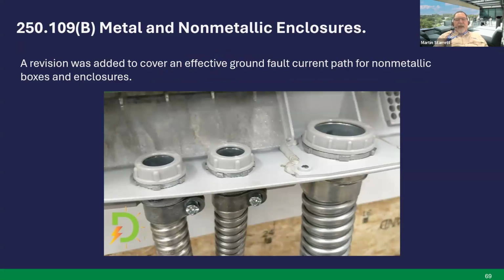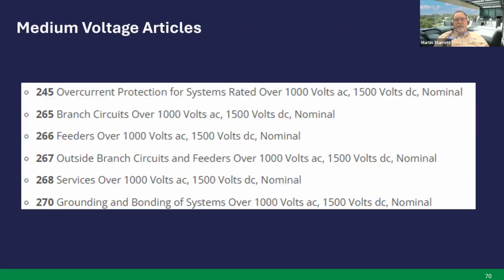250.109(B), metal and non-metallic enclosures. A revision was added to cover an effective ground fault current path for non-metallic boxes and enclosures where metal pipe and raceways come into these non-metallic boxes. It tells you how to do your effective ground fault current path for these whenever you do this. We already had it for metal, but now we'll have it for non-metallic enclosures.